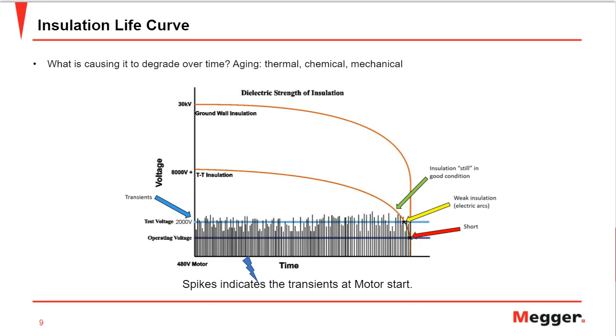So the spikes which you see indicate the transients which the motor sees whenever it starts. Looking at the shape of the graph, we can tell that the insulation reaches a particular level and then it plunges quickly. Once it reaches the motor start voltage, which is usually around five times the per unit value of the terminal or rated voltage, we see more voltage arcing happening, and more often that ends in motor failure, which is the bus voltage or the operating voltage of that motor. And there are various causes for insulation degradation, like thermal, chemical, and mechanical wear and tear.